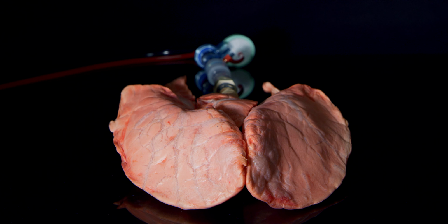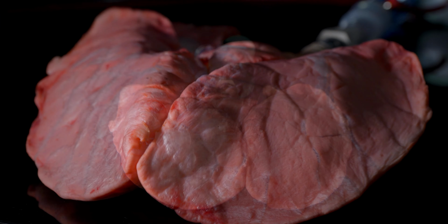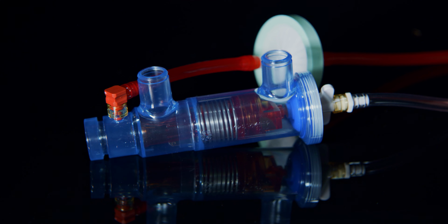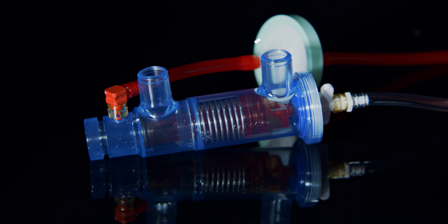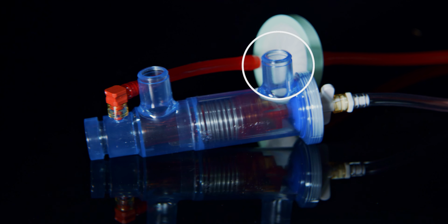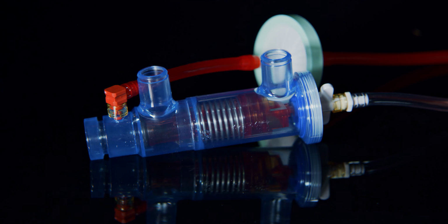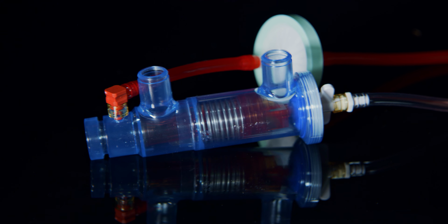The key to the TXP5's ability to maintain mean airway pressure at all levels of compliance change is the unique valving system. Gas is entrained to only meet needed set pressures, and the open exhalation system allows counter-current expired gas to exit out.